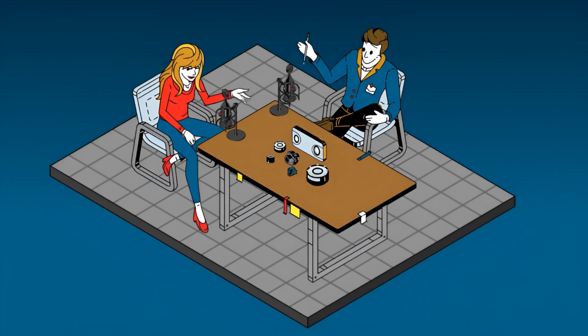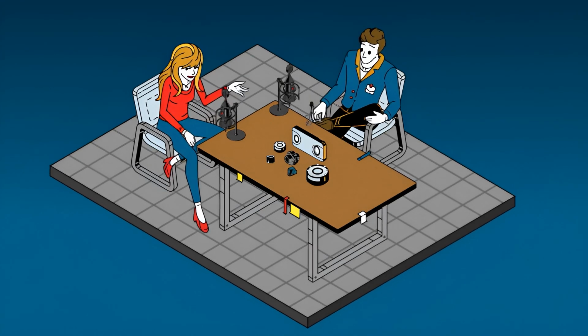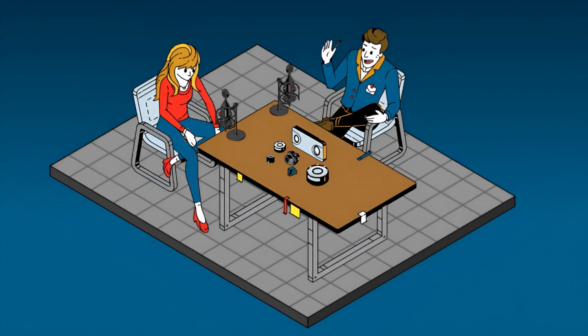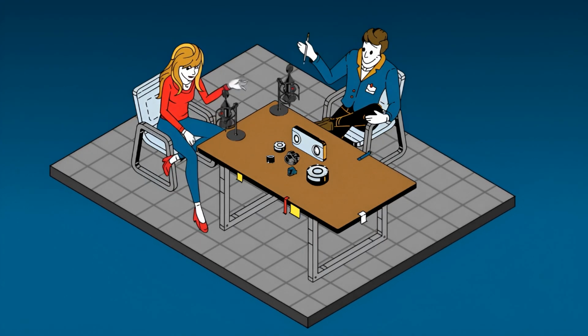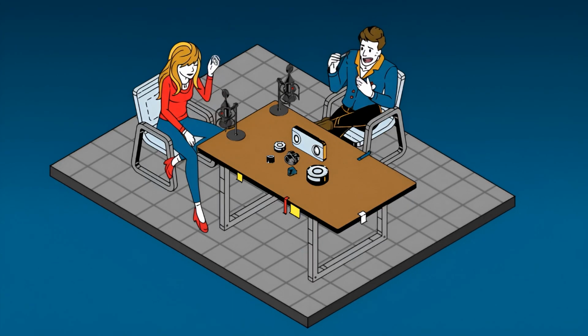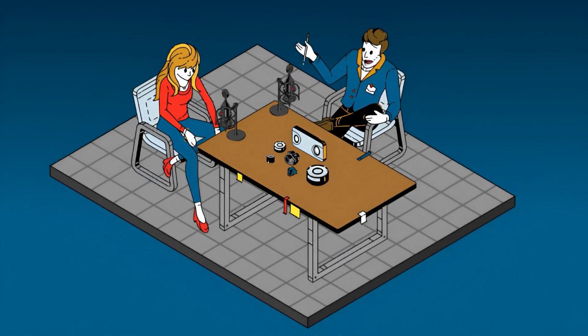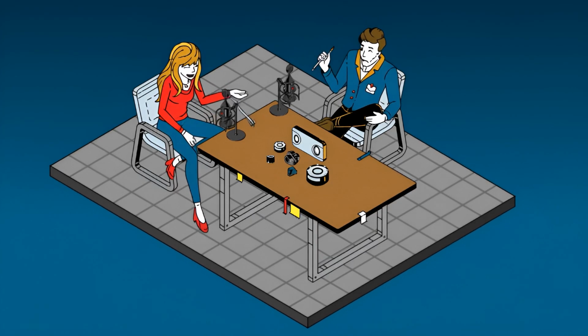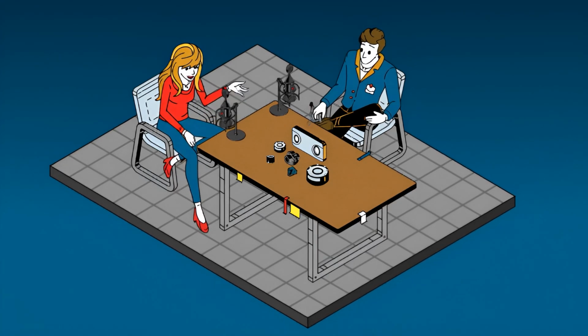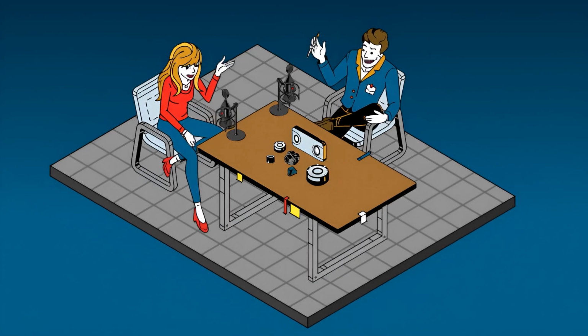This highlights why the flexure itself is so critical. Its design, shape, and material are all optimized by engineers based on factors like the load capacity needed, physical size constraints, temperature changes, even altitude, since air pressure can matter in highly sensitive measurements. Critically, engineers also consider how sensitive it needs to be to side forces, called extraneous loads, since force isn't always applied perfectly straight on in the real world. It's a real balancing act between material science and mechanical design.